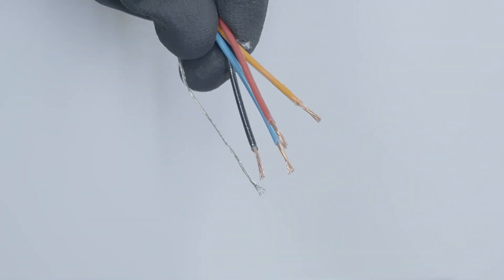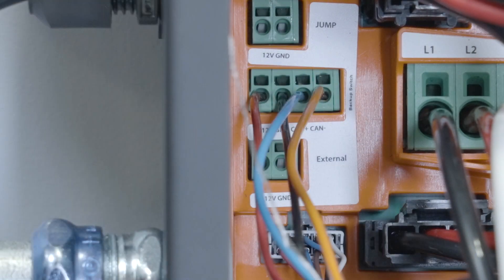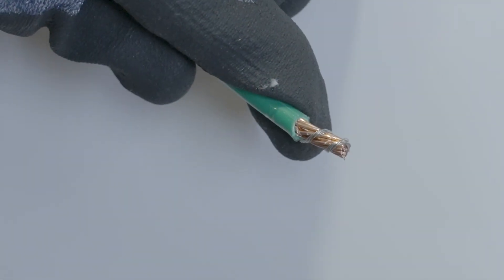Terminate the four conductors of a shielded, twisted communication cable in the solar assembly, taking note of the labels of each conductor. Twist the drain wire around the bare copper of an equipment grounding conductor and terminate in the ground terminals of the solar assembly.